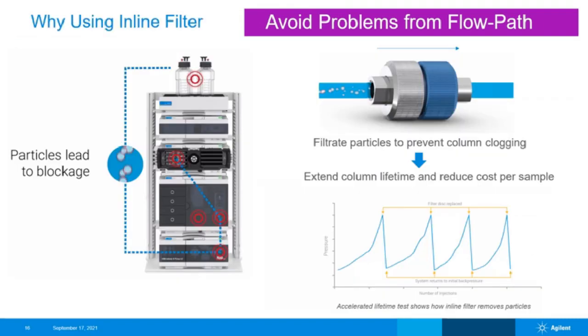Why should HPLC users use inline filter? Particles can come from everywhere in the flow path. Solvents, samples, or worn instrument parts such as pump frits or rotor seal of injection valves. Over time, particles can clog the column frit, causing pressure increases that damage LC columns and shorten their lifetime. An inline filter protects valuable columns by capturing particles before they reach the column, extending their use and reducing the cost per sample.